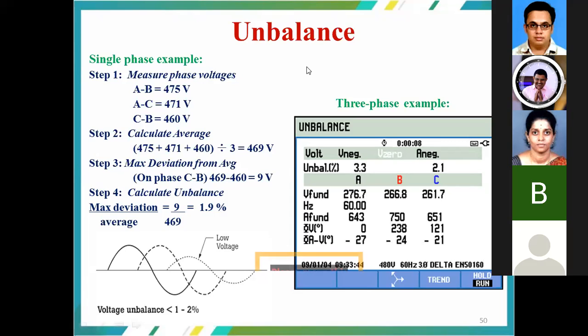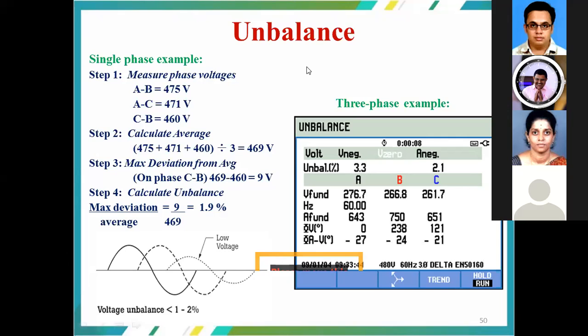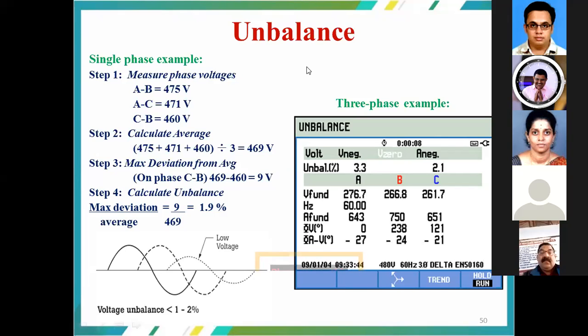So for example, in the given condition, the line-to-line voltage between A and B is 475, between A and C is 471, and between C and B is 460. So the A-B and A-C lines have almost the nearest voltages, whereas C to B has 460 volts. The average of these three voltages is almost equal to 469. Again, the difference for C to B is going to be 9 volts. So 9 volts of the average is going to be 1.9 percent, which is a higher limit.